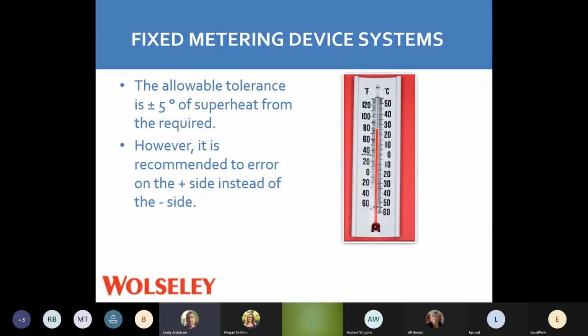So fixed metering device systems, we always have a tolerance. Doesn't matter what we're dealing with. If we're dealing with electrical or freon, we always have that plus or minus tolerance. We always want to go to the plus side and not so much to a minus side. Same thing with refrigeration and our readings. We always have that little bit of a tolerance that we can play with.